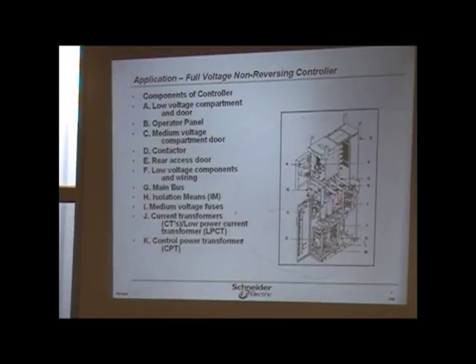All it does is identify where the fuses are at. The medium voltage fuses, which is I, are right here. Then the current transformers, the control power transformers, where it's J, the CPTs, the CTs, and everything are all down in here. D shows the contactor itself. And of course, this is the door itself, the medium voltage compartment door, that's what it's pointing up to.